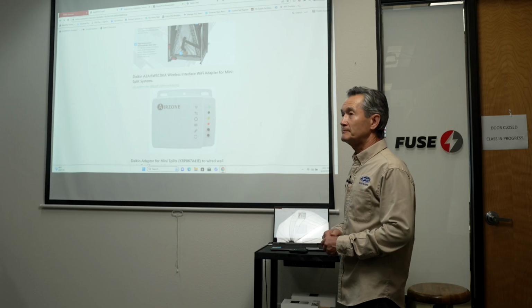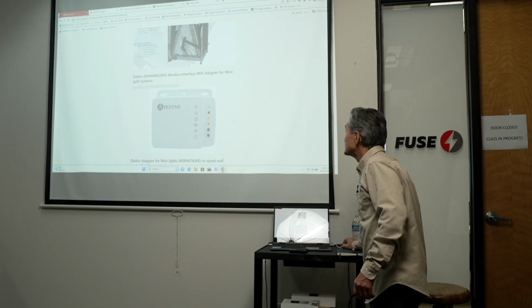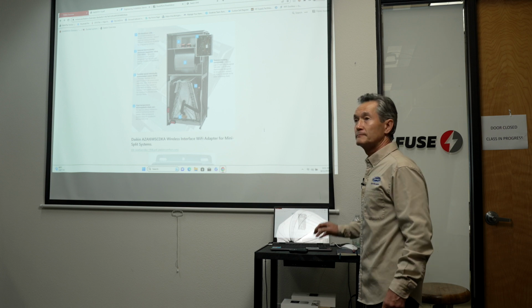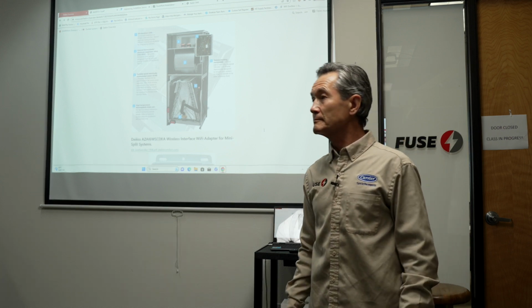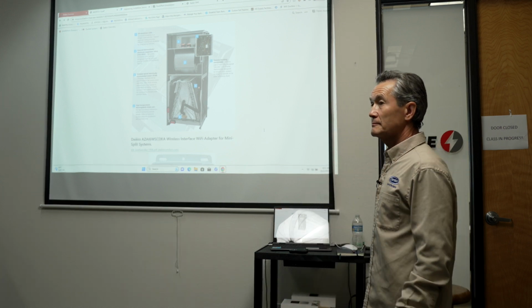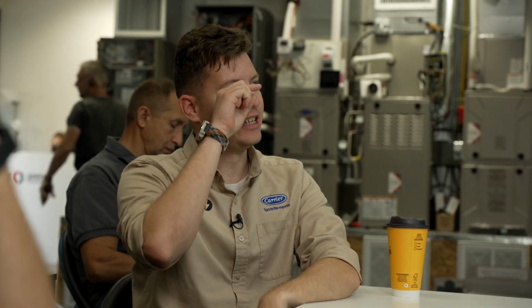I'd like to add about the air handlers - keep in mind, this type of air handler does not allow side returns. The second thing is if we install the unit downflow, not upflow, it requires a downflow kit. So the unit has to be modified on the side a little bit if you install it downflow, okay?